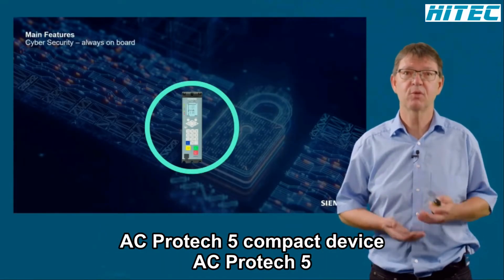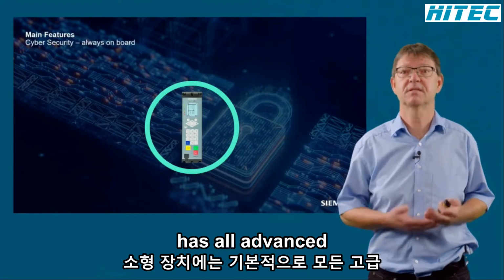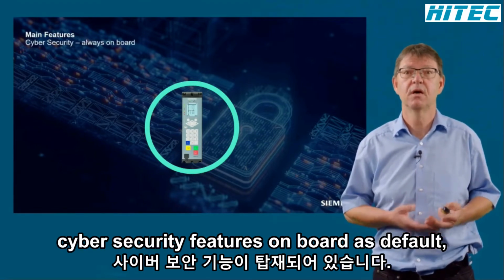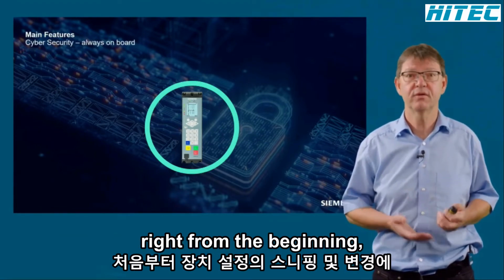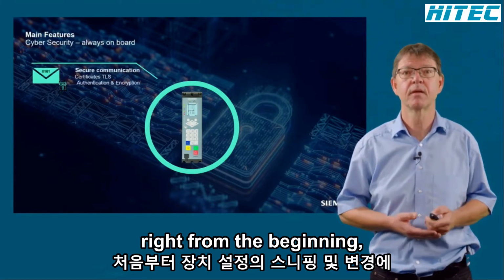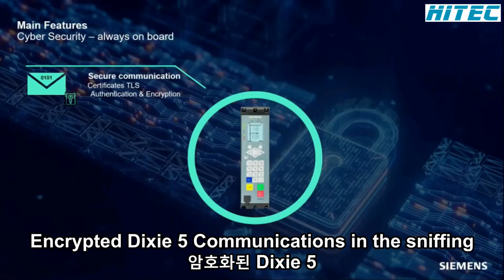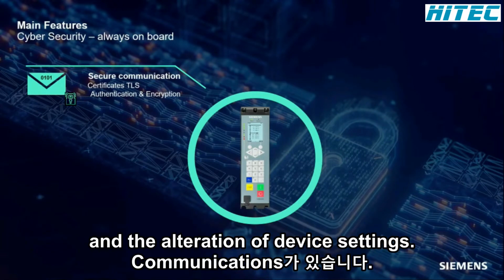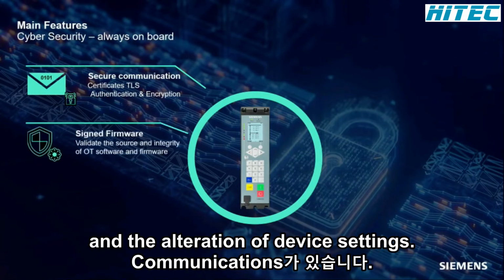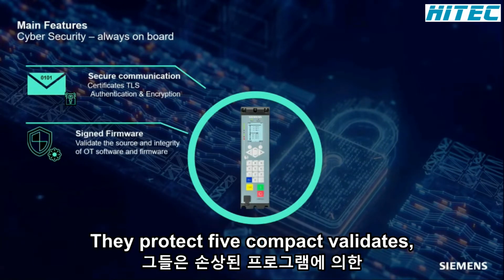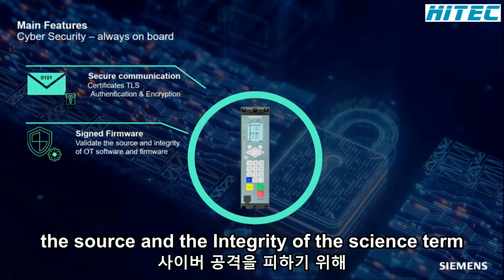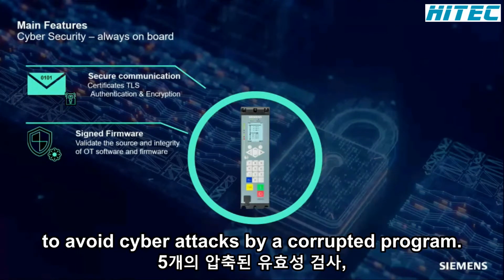The SIPROTEC 5 Compact device has all advanced cybersecurity features on board as default right from the beginning. Encrypted DIGSI 5 communications hinder sniffing and the alteration of device settings. SIPROTEC 5 Compact validates the source and the integrity of the signed firmware to avoid cyber attacks via a corrupted firmware.